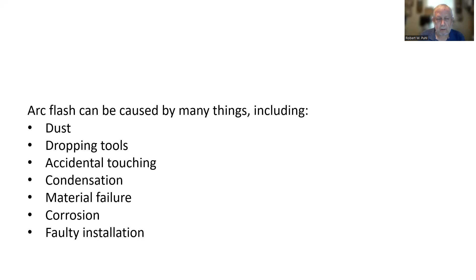Faulty installation too. Three factors determine the severity of arc flash injury: proximity of the worker to the hazard, temperature, time for the circuit to break, and response time of the circuit interruption. Part of the arc flash hazard incident analysis is usually done by an electrical engineer. They have to know the response time of the circuit interruption - the breaker or the fuses - and how long it's going to take for that thing to open up before they can determine what the arc flash hazard is going to be like.